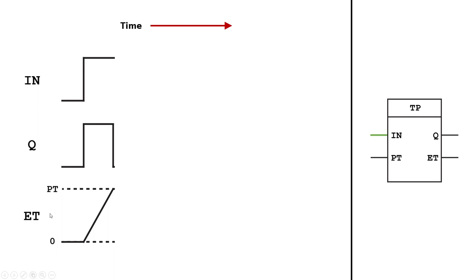The elapsed time also starts counting as soon as I turn on the input. When the elapsed time has reached the preset time — which is the length of our pulse — the output will be deactivated again. So what we've generated through the output is a pulse of a certain length.